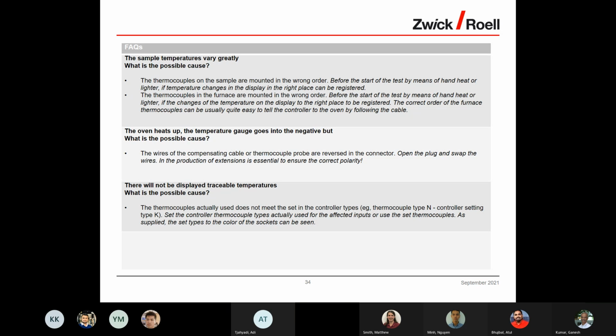The thermocouples in the furnace are mounted in the wrong order. Before the start of the test, by means of hand heat or lighter, check if the changes of the temperature on the display are registered in the right place. The correct order of the furnace thermocouples can usually be quite easily determined from the connector to the oven by following the cable.